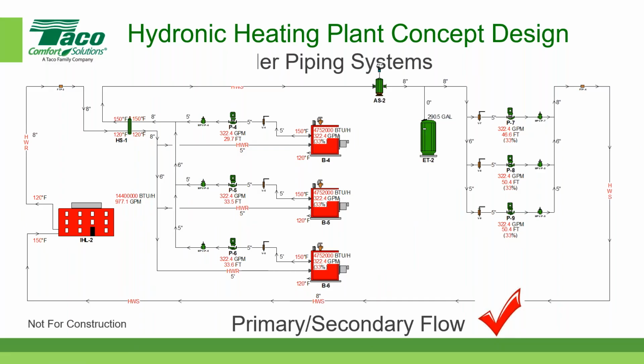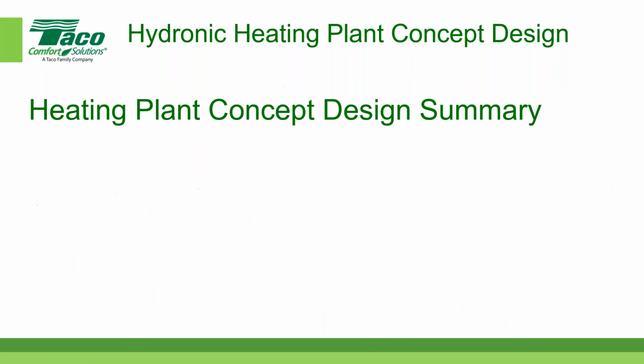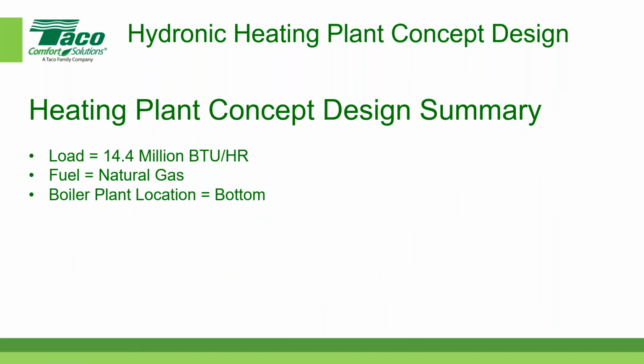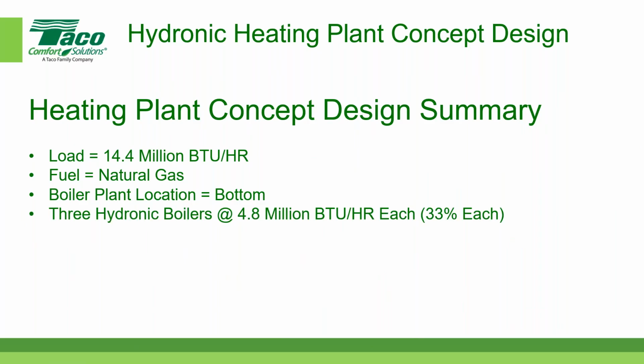I think that's it. Let's see what we got here. Oh, this is just a summary of all the decisions that we made for the concept design. We did a very simple load estimate, and we said the building was 30 BTUs per hour per square foot. Multiply that by the square footage, it came out to 14.4 million BTUs per hour. We decided the fuel would be natural gas. The boiler plant location is at the bottom of the building, usually on the first floor, or if there's a basement, usually in the basement. We also decided to have 3 hydronic boilers at 4.8 million BTUs per hour. So that means that each boiler is 33% of the total load.